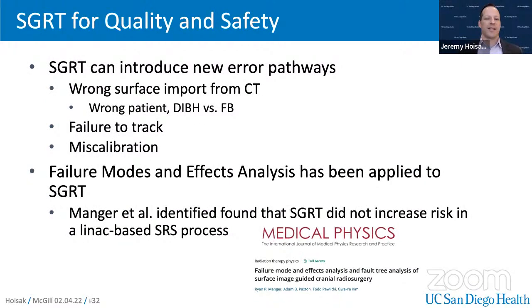I will say, though, that SGRT can introduce new error pathways that may not necessarily have been there before. One of the major error pathways for SGRT is that you can import the wrong CT surface. You can imagine that would be quite bad for trying to localize the patient. A similar error is that you may not import the wrong patient, but, say, if you're looking at a deep inspiration surface versus a free breathing surface, you could import the wrong one or get them labeled wrong.